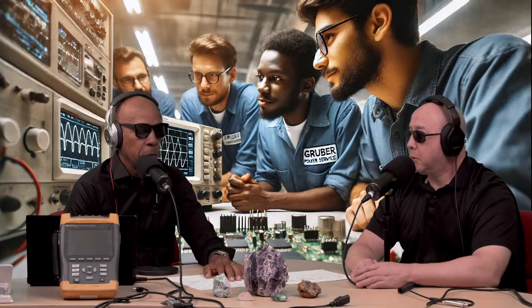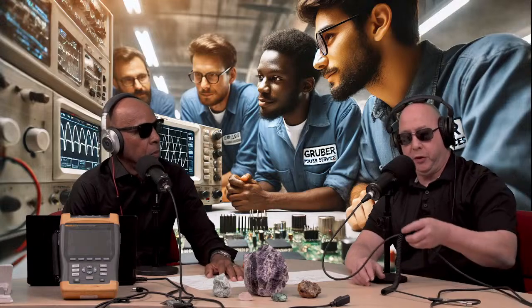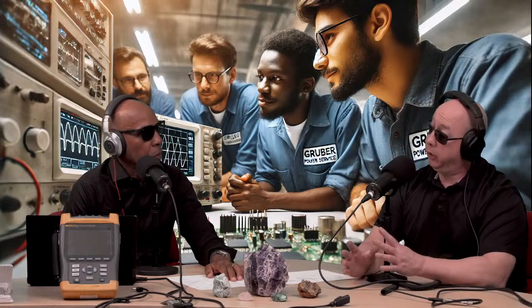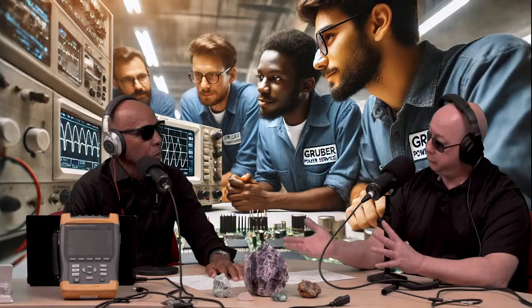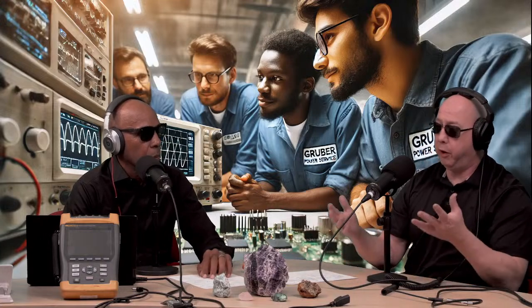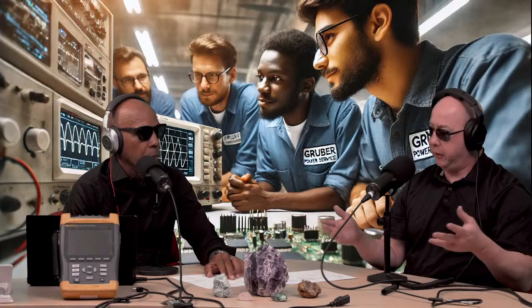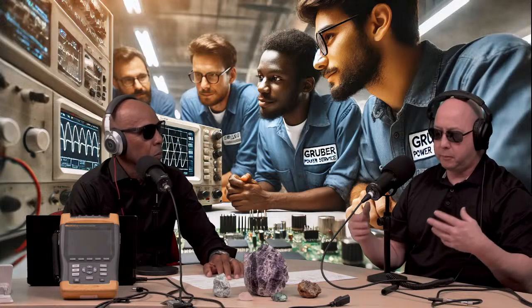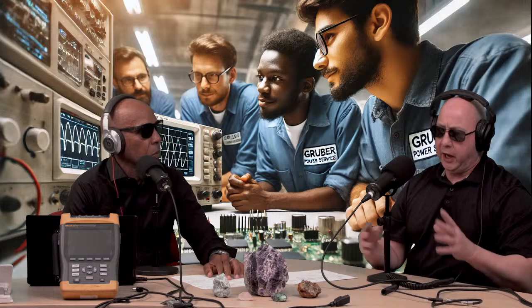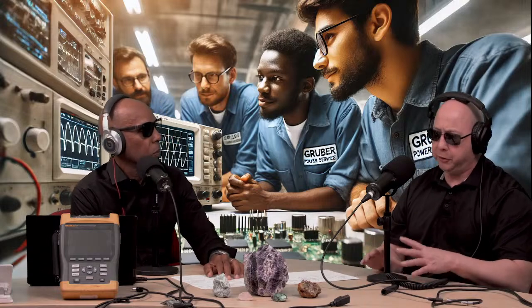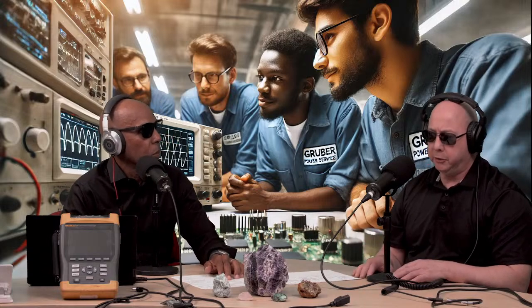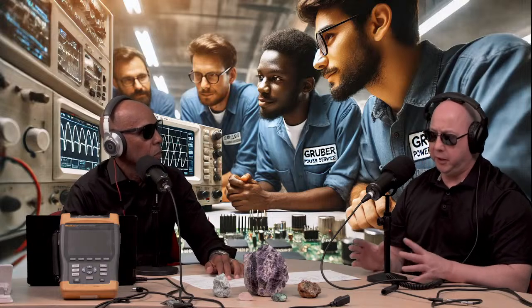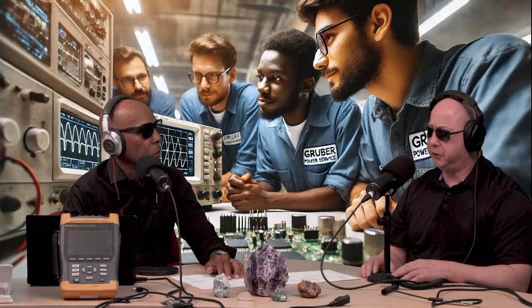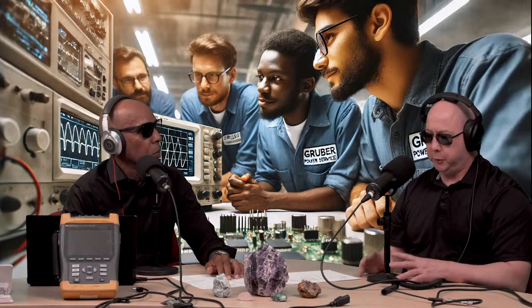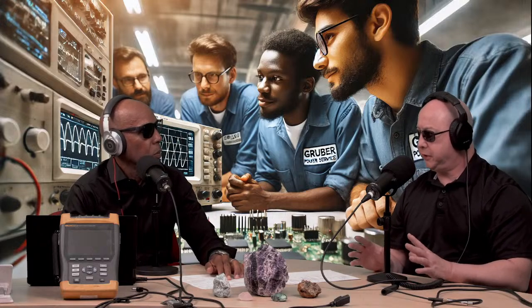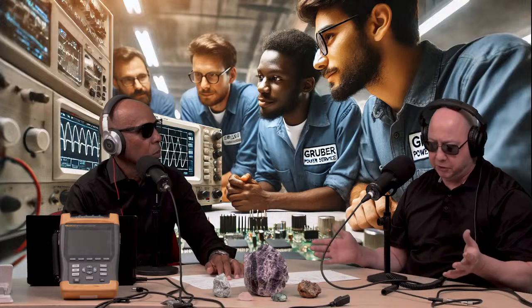That's basically what we do initially — just let it run and heat up too, because components can fail due to heat. So we'll let it run for half an hour to an hour just to get everything warmed up, because you can have a failure before you put any load on it or stress the unit, just from heat itself. Heat can affect a component that's just sitting there, and all of a sudden it fails.